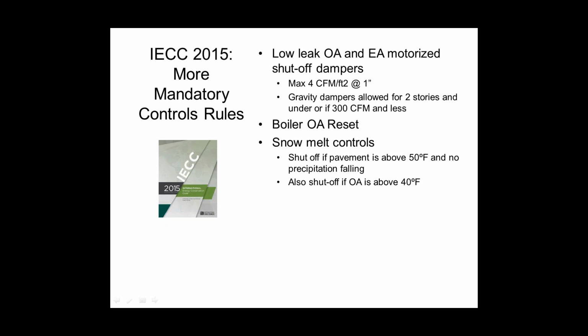You shut it off if the pavement's above 50 and there's no precipitation falling, so you have to have a sensor that senses moisture as well. And then you also have to have a shutoff if it's above 40 degrees of outdoor air temperature. So you have 3 different shutoffs that you have to have on a snow melt system to prevent heating when it's not needed.